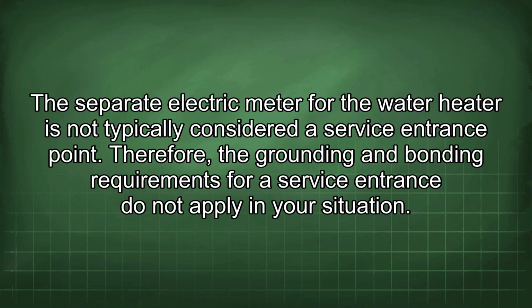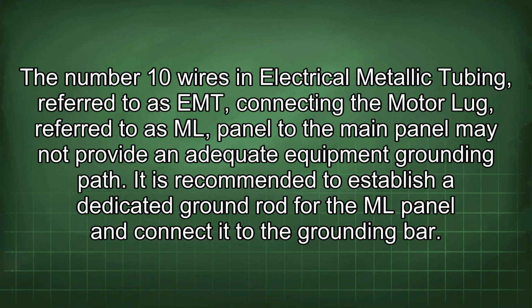The separate electric meter for the water heater is not typically considered a service entrance point. Therefore, the grounding and bonding requirements for a service entrance do not apply in your situation. The number 10 wires in electrical metallic tubing, referred to as EMT, connecting the motor lug, referred to as ML, panel, to the main panel may not provide an adequate equipment grounding path.